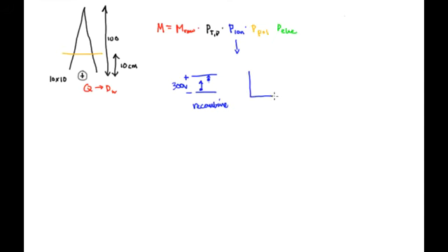So you can make a plot here of the charge that's collected versus the voltage. And at a low voltage, it's not very efficient because there's lots of recombination happening as it drifts slowly. As you increase the voltage, more charge is collected and then it kind of saturates. So this is a typical curve. The size of this effect is pretty small. It's never more than 2% for chambers, but still we have to correct for it to do accurate dosimetry.